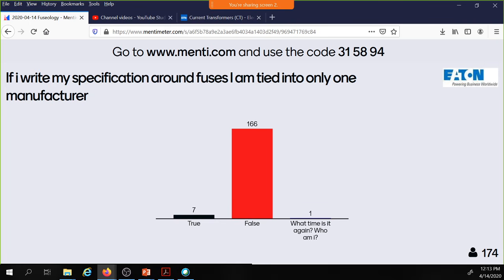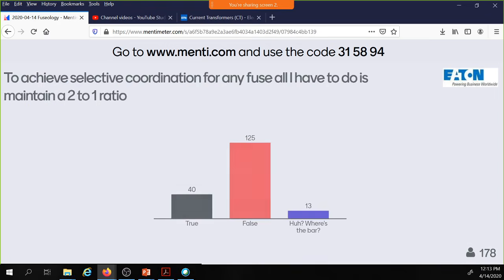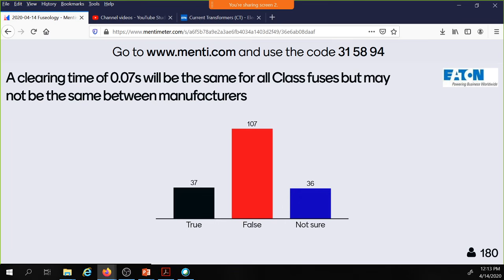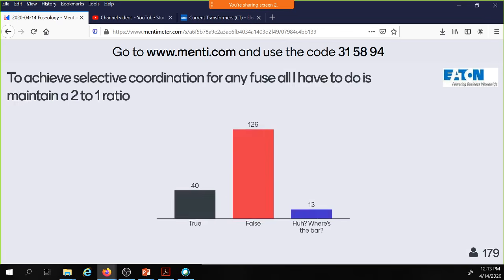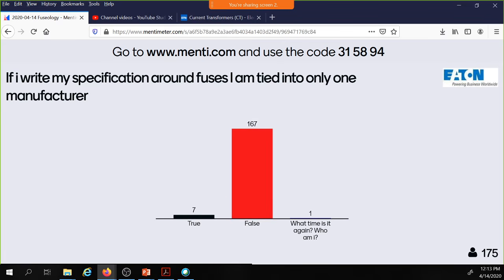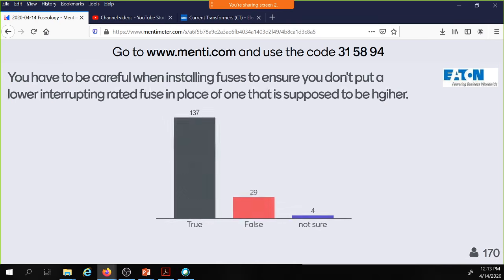So the clearing time of 0.07 seconds is true. That is the 0.07 second question. The answer was false, because every fuse curve is probably going to be different, especially if it's different between manufacturers. All right. Hopefully that answered your question. And the right answer on this one is, again, false, because of the reasons I just said. If you wrote a spec around a fuse, you automatically meet 3 manufacturers who would be able to quote that job very easily.